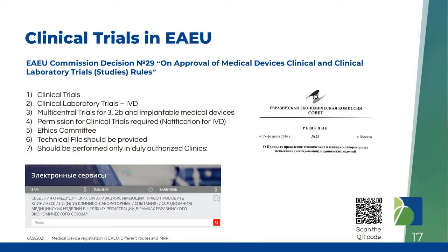For IVD products, you should submit a notification. Permission is not required. So please review chapter 4 of the decision number 29. You should get the permission from the competent authority of the reference country. The procedure is described in chapter 4.19.